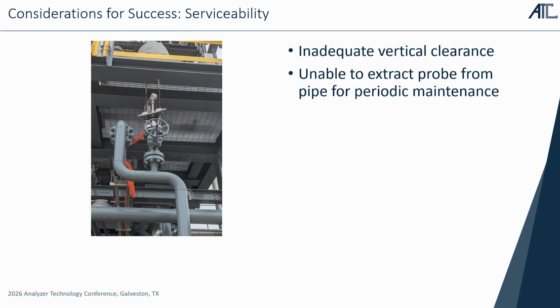Here's an example where we did everything right. We put it together, it gets handed off to the construction crew, and there's no serviceability here. They installed the probe into the pipe, then welded the pipe up underneath an I-beam. That should be a probe that gets extracted out, that's an extractor assembly, but there's not enough vertical clearance between the top of the probe and the bottom of the I-beam. That probe's never coming out.